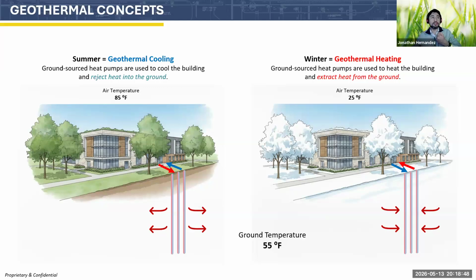And when the winter comes, you're, let's say, now at a ground temperature of 55 degrees F, and the air temperature is still below freezing at 25 Fahrenheit. You cannot rely on an air source heat pump to produce heat during a blizzard efficiently. That pump is going to work a lot harder, and you're going to not see the savings that you were promised, as with the standing column well. So when you have a ground temperature that is consistent and or pre-charged, your coefficients of performance, your efficiencies, shoot up during the peak seasons. This is when geothermal truly is the star of the show.